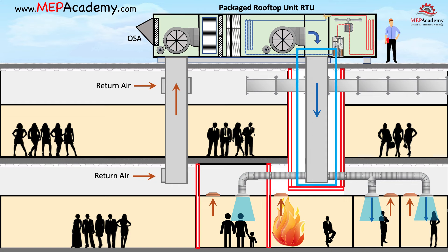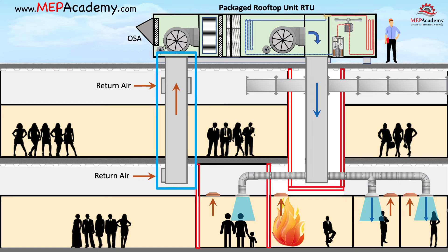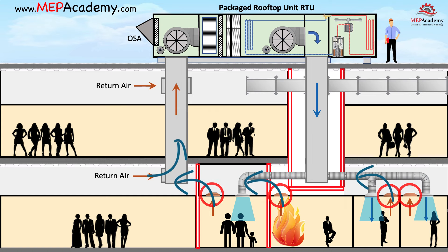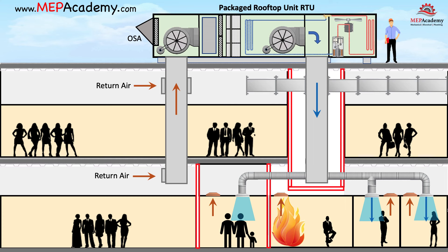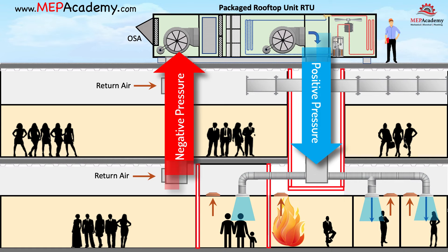A main supply air duct feeds all of the first floor spaces and is returned using an attic return from the spaces into the main return air riser. Each of the spaces will receive a connecting supply air duct and a return air grill that lets the air find its way back to the air conditioner through the return main. The fan in the air conditioner creates a positive pressure on the supply side pushing the air through the duct, while the return side creates a negative pressure and pulls the air back to the AC unit.